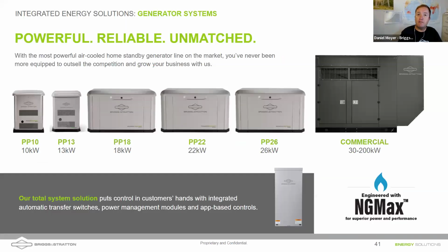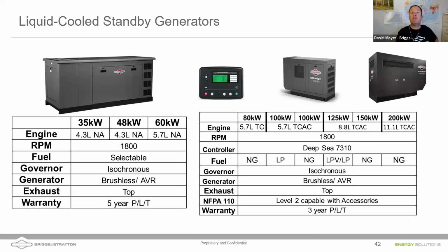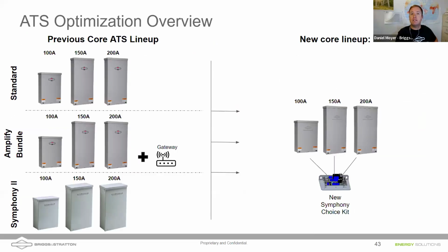Here's the generator lineup. One thing I will call out is our NG Max. A lot of generators, say a 22K generator, operate at 22K on propane, but as soon as you run it on natural gas, it derates down to maybe 18.5. With our NG Max, we're able to get all of that 22K out of natural gas as well. Then larger air-cooled commercial, and liquid-cooled standby generators as well. This would be a great pairing for that 30 and 60K.